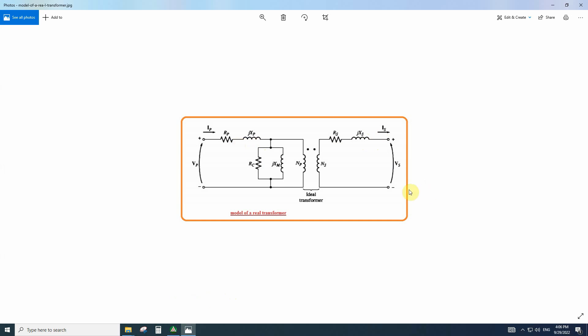We perform the short circuit test and open circuit test to determine the equivalent circuit parameters. The open circuit test helps us determine the parallel branches of the equivalent circuit, because the input and output current is very low — we can find the magnetization inductance and the resistance that represents the core loss in the transformer. To figure out the leakage inductance and the resistance of the transformer, we perform the short circuit test. In short circuit, the voltages are very low, so the parallel branch can be neglected and we can determine the leakage inductance and resistance.